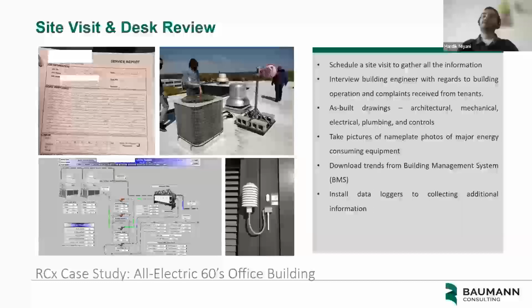For example, for this particular building, there was a cooling tower. They had the nameplate on the cooling tower, but it did not have the motor rating on it. So with the model number, we were able to directly reach out to the manufacturer representative to get all the information that we needed in order to perform all the engineering calculations.